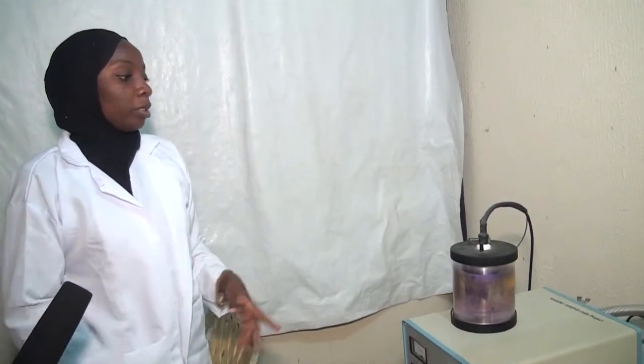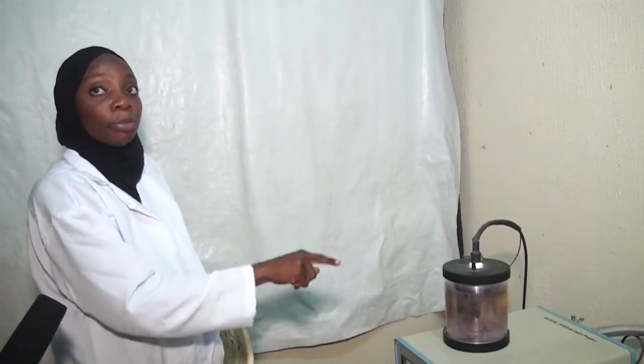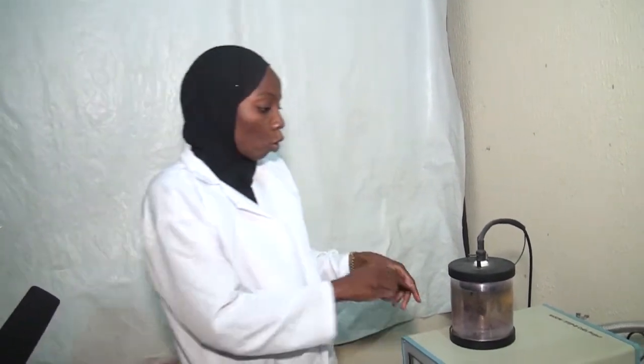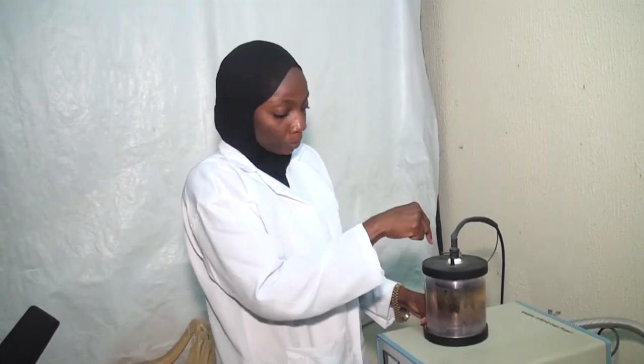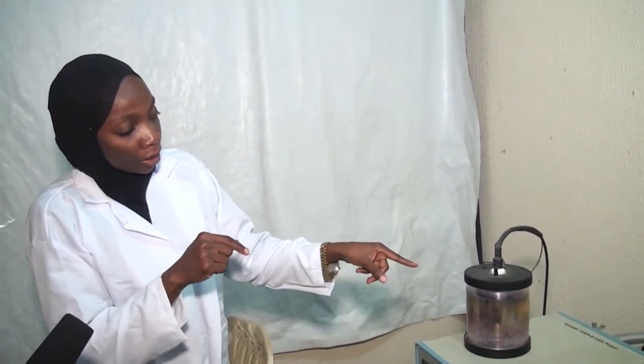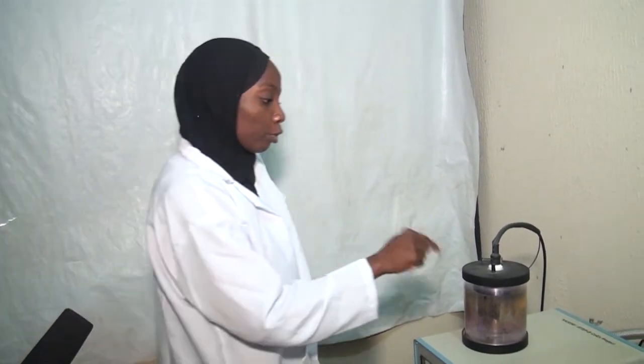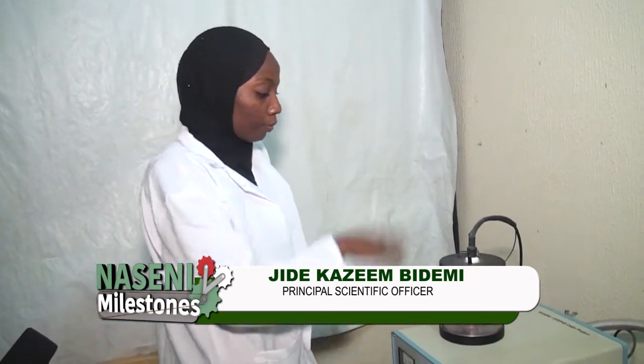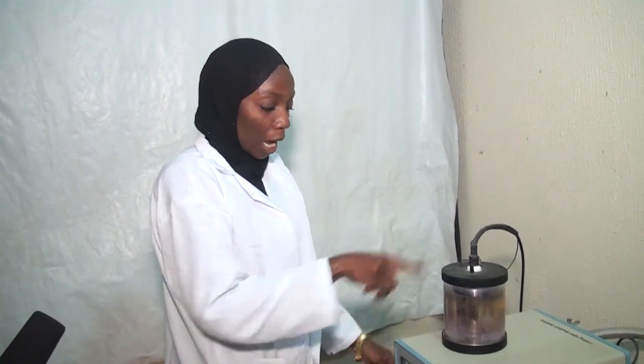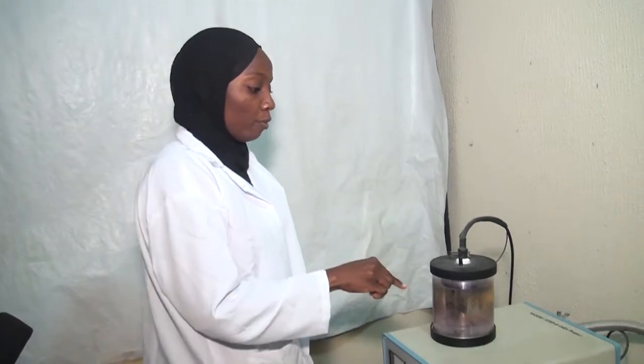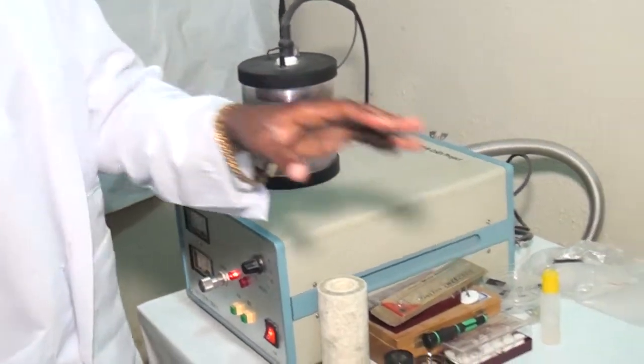The machine utilizes an electric field and argon gas. With the electric field, electrons are removed from the argon gas, making it positively charged. Then this positively charged argon becomes attracted to the gold foil inside the system, thereby ejecting, removing an atom from the gold foil. The gold atom will then fall on the sample and coat its surface with a thin layer of gold.